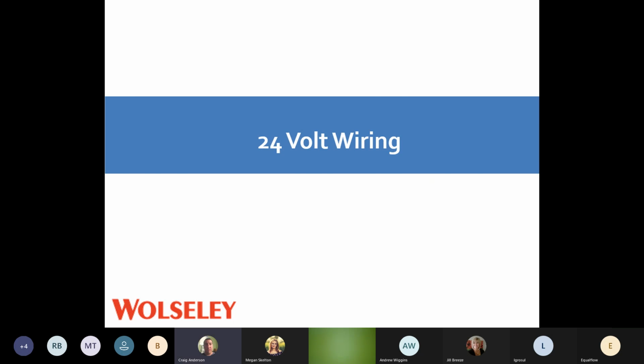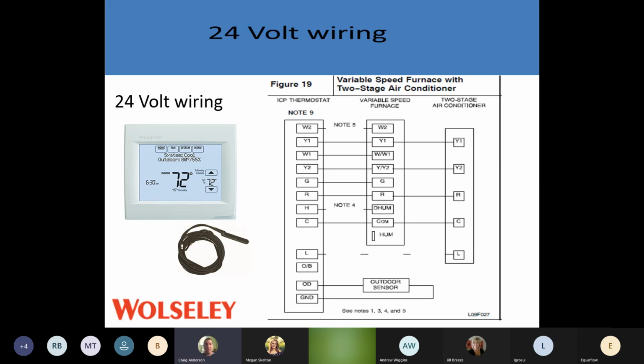24 volt wiring. Now we're testing our unit to make sure it comes on. So if we're dealing with a two-stage air conditioner, we're going to have a Y1, Y2 outside, which is our staging for our compressor outside. Some units will have an R terminal. So when that air conditioner turns on, we should have 24 volts on R, and then we should have 24 volts on Y1, Y2, depending what stage it's on. Always go from your common to whatever you're testing on your 24 volt side.